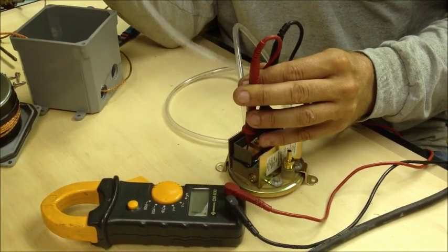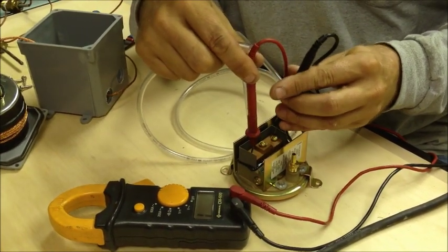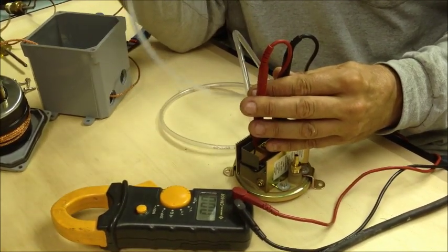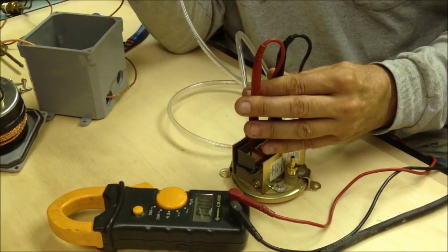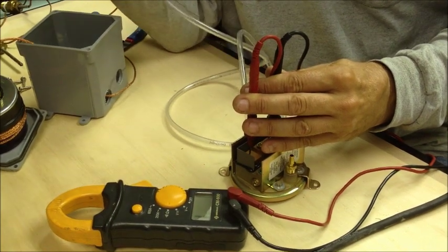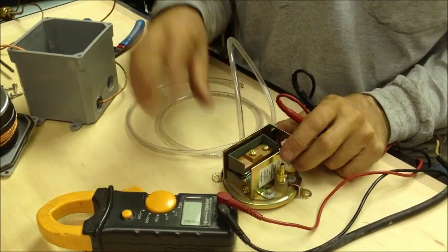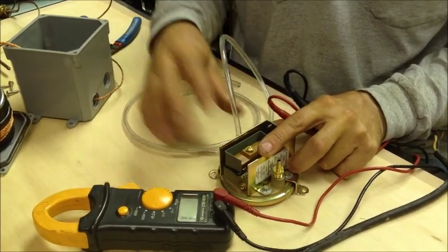When we release it, it should open. We can check also the normally closed where it will be buzzing, closed circuit. We put a vacuum on the low pressure port, it opens, we release, it closes. So we know that the low pressure side or the vacuum side of this switch is good.